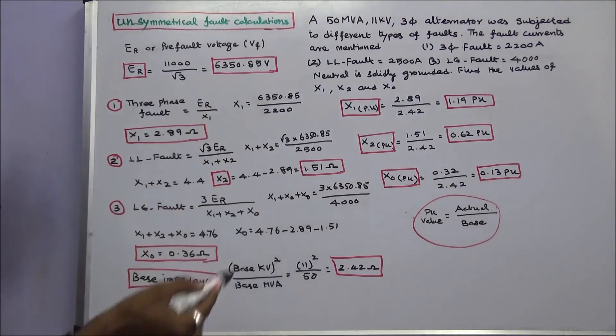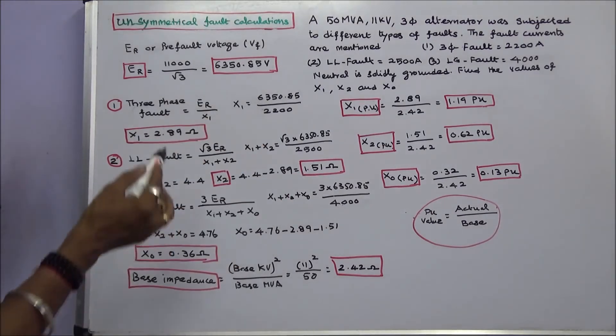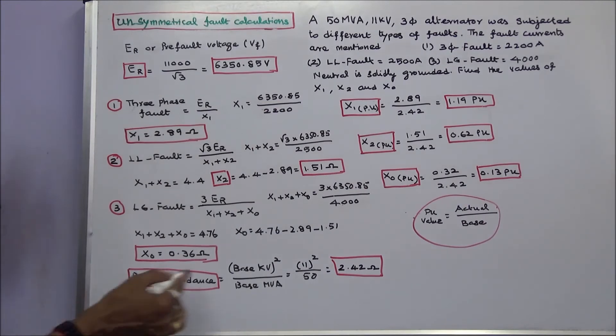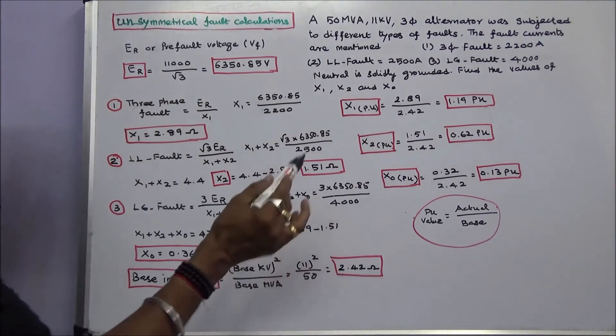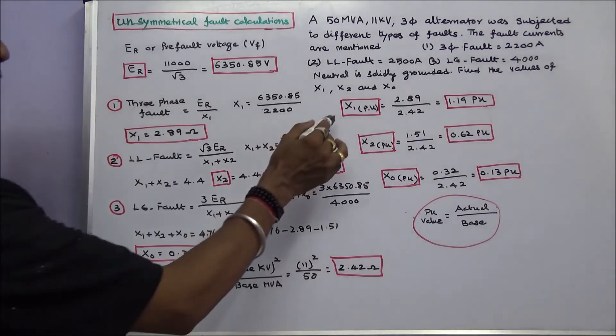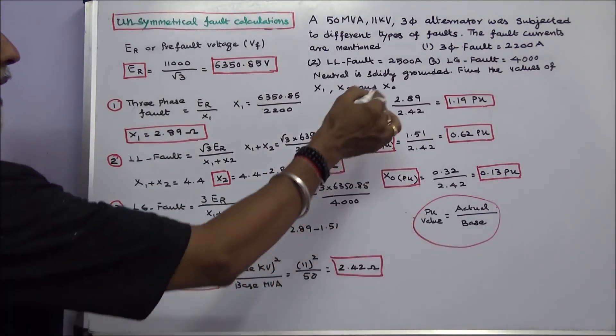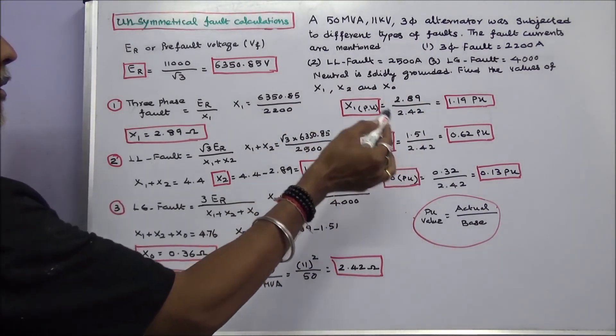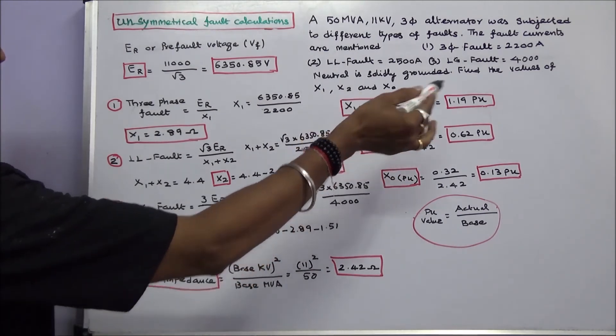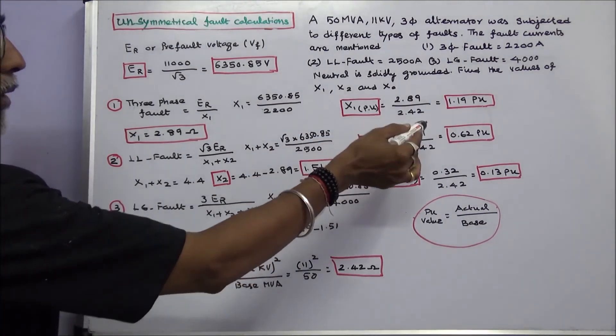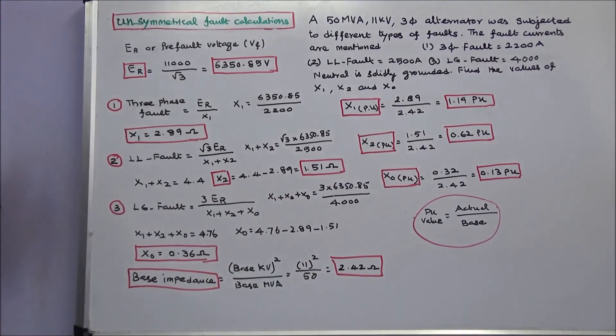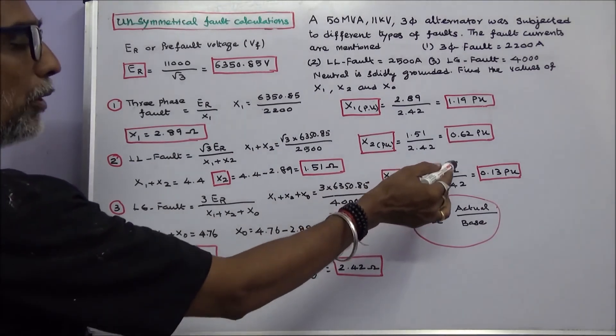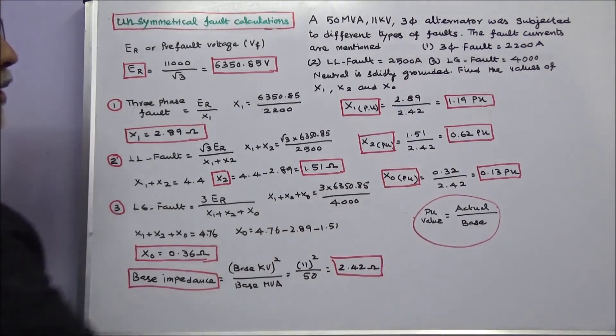To convert all values to per unit, we find the base impedance. Base impedance equals base kV squared divided by base MVA, which is 11 squared divided by 50, equal to 2.42 ohms. So X1 per unit is 2.89 divided by 2.42, equal to 1.19 per unit. X2 per unit is 1.51 divided by 2.42, equal to 0.62 per unit. X0 per unit is 0.36 divided by 2.42, equal to 0.13 per unit.